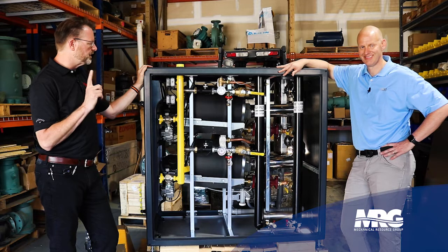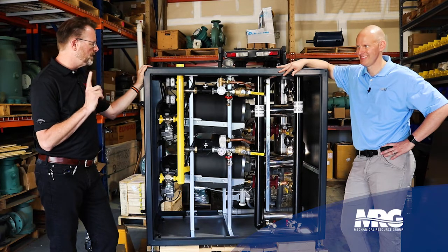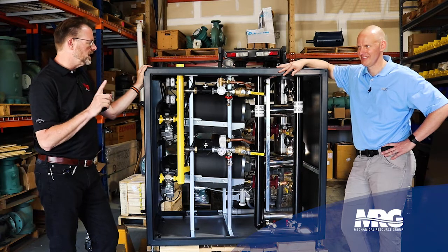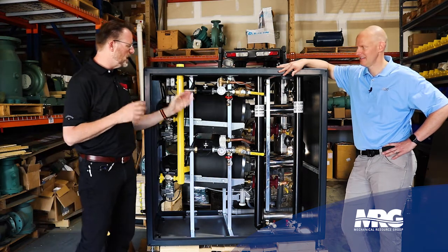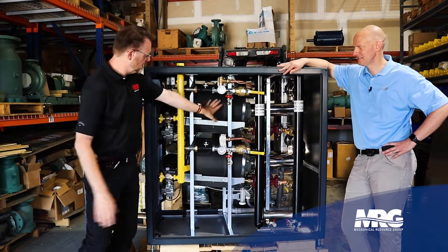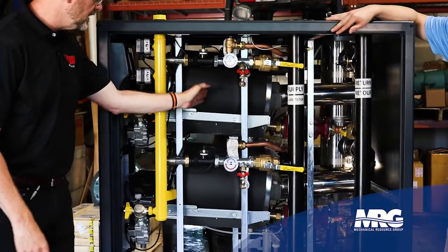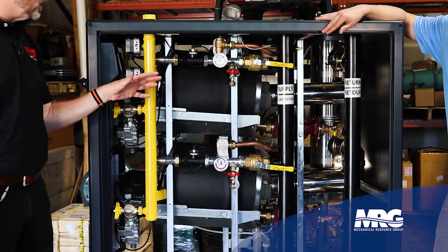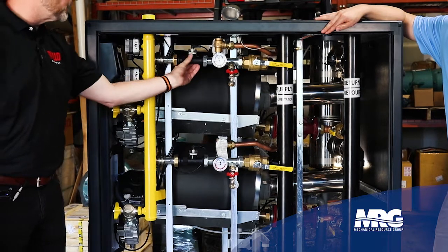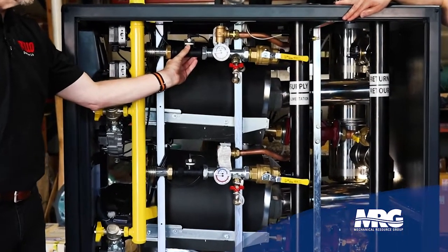As I recall, one was a flow switch. We had a unit that had a bad flow switch. The lack of being able to prove flow resulted in the loss of the entire unit's capacity. What I responded with was, we do prove flow on each of the helix heat engines, the fired heat exchanger with a circulating system. We prove flow continuously on each unit with a flow meter, not a flow switch.